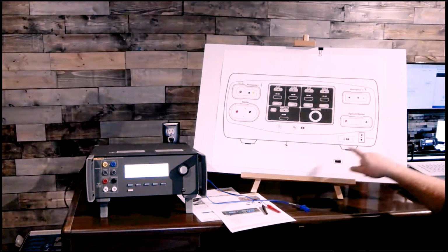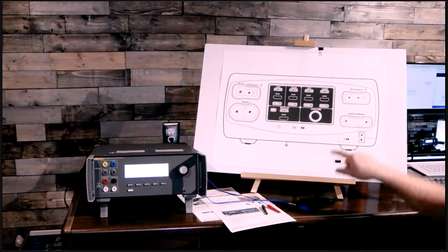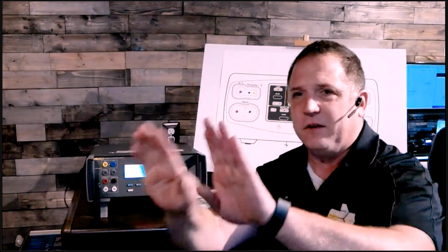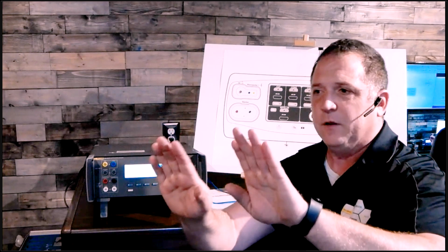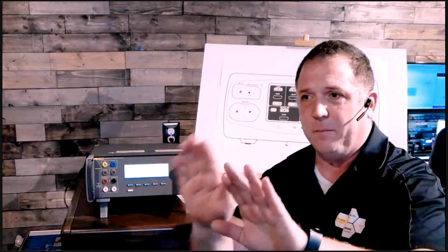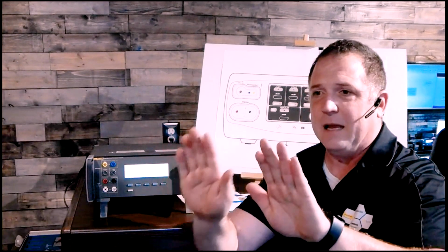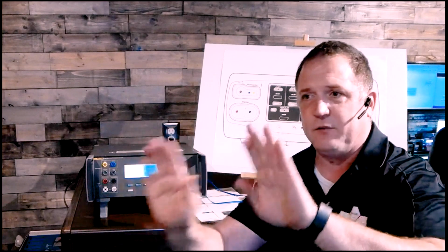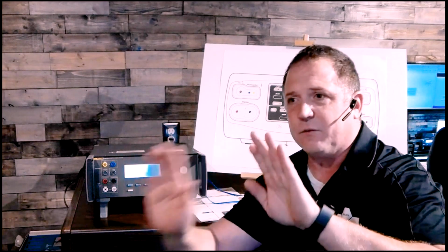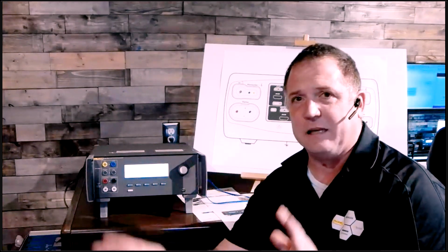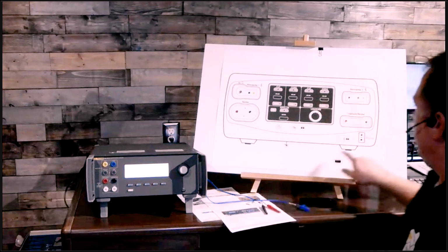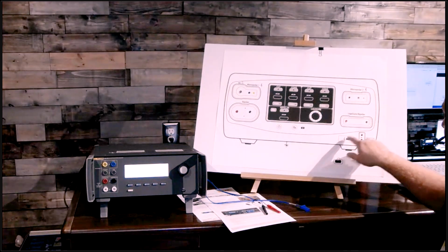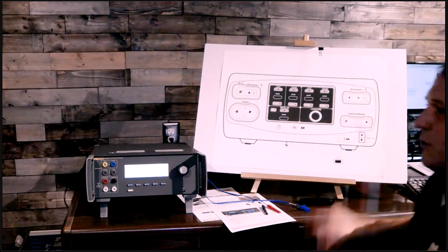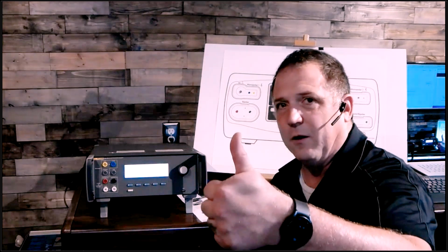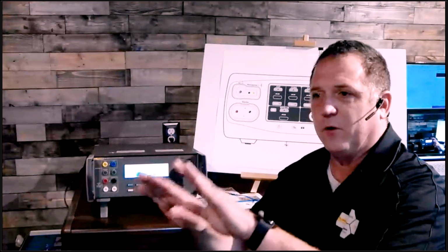So the idea behind the dual foil pad is that we can measure the resistance between the two foils. The REM or CQM built into your ESU checks how much resistance is between these two foils, and as long as it's within tolerance, it lets the ESU operate. When you plug this in, you'll normally see the light turn from red to green, saying we're good to go.